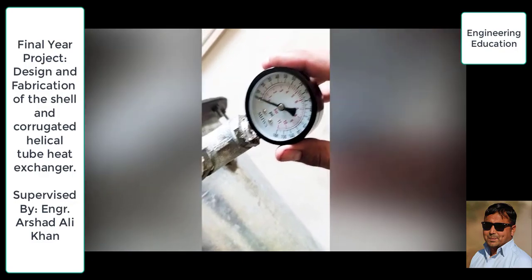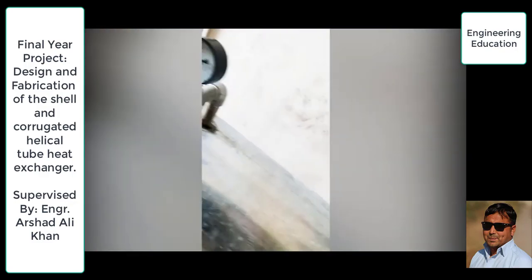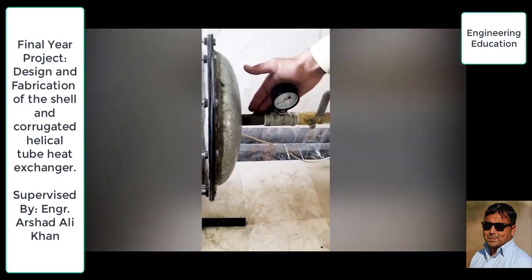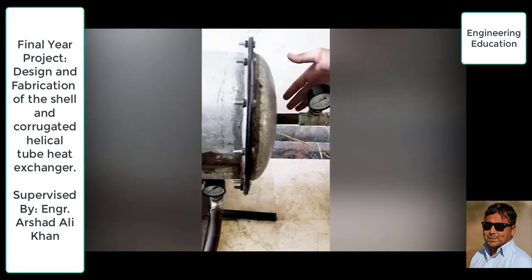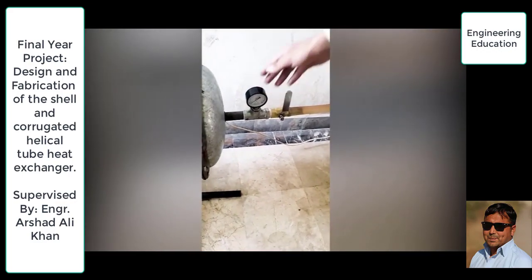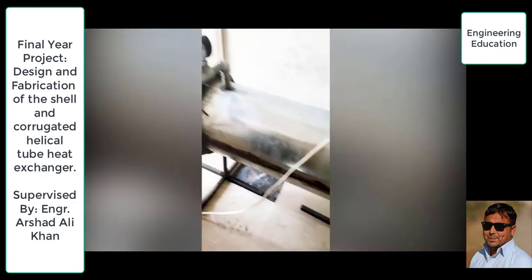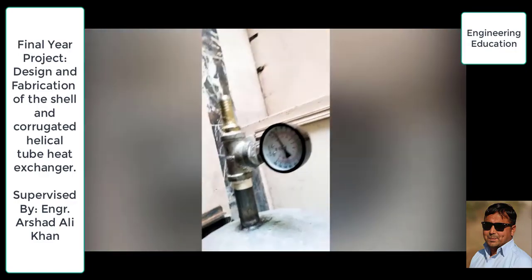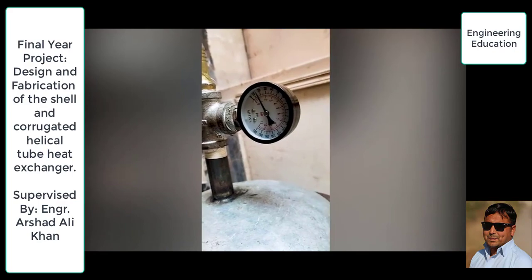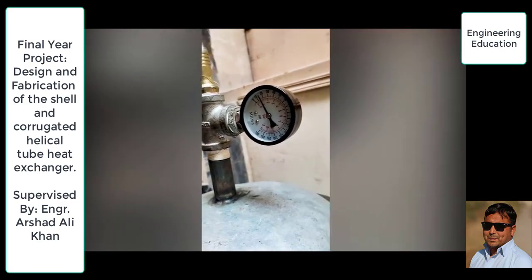Here are the pressure gauges: this is the inlet pressure gauge of the shell side, and here is the inlet pressure gauge of the tube side, through which water flows from the corrugated tubes and the pressure readings are shown. On the other side there is the same pressure gauge with the same range, and the pressure drop across the tubes will be obtained by calculating the difference between these two pressure gauge readings.